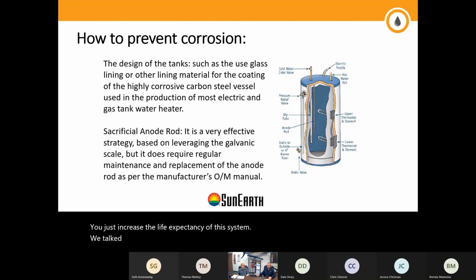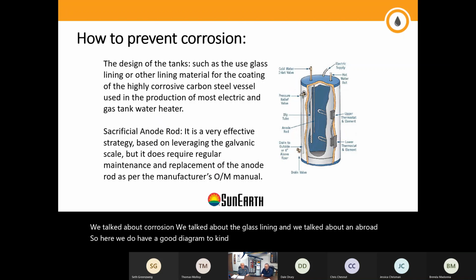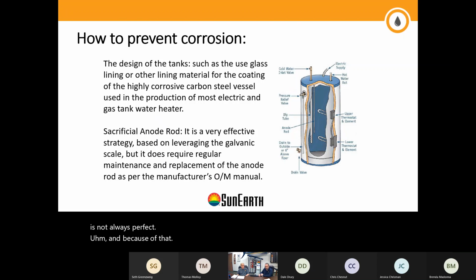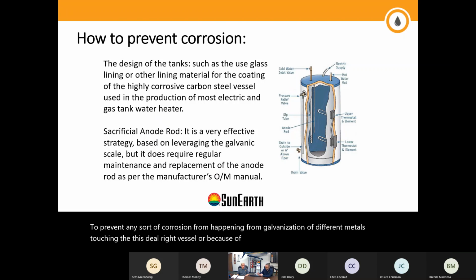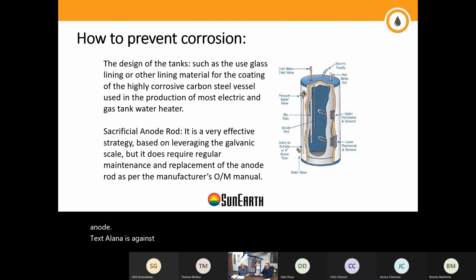We talked about corrosion, we talked about the glass lining, and we talked about the anode rod. So here we do have a good diagram to get into the detail. As Bob was mentioning, most of the tanks are steel, and they come with a glass lining or other type of lining. That lining is not always perfect, and because of that, to prevent any sort of corrosion from happening from galvanization of different metals touching the steel vessel, or because of the electrolysis process, you have a sacrificial anode. The name says it: it's there to be sacrificed to protect the system. And Bob, if you want to get into the details of how it works, how you check it, how to change it.